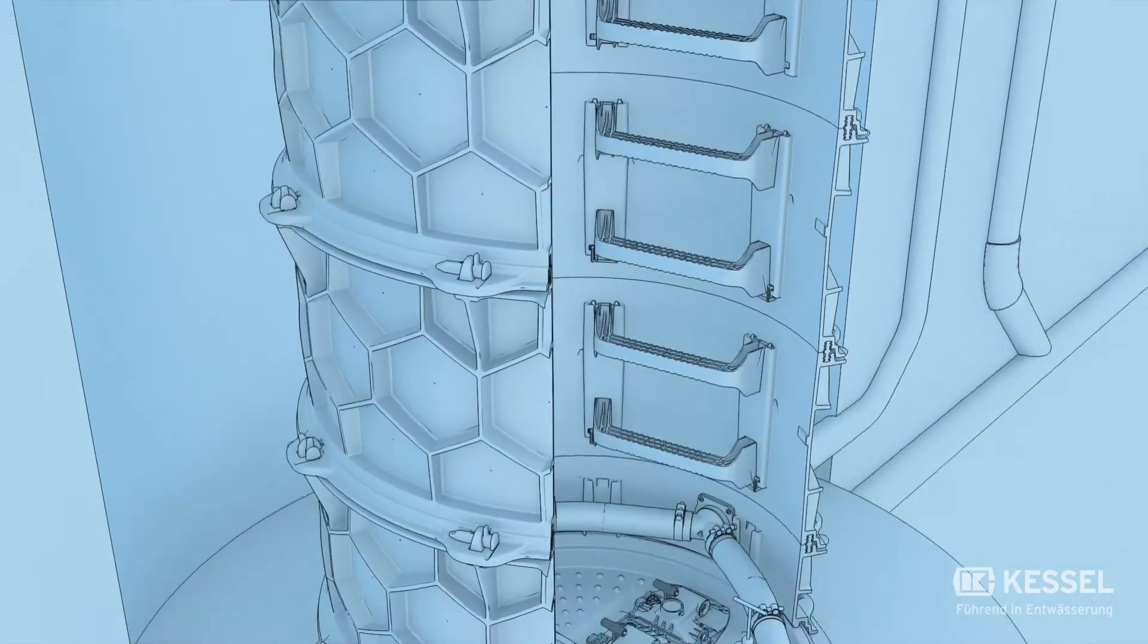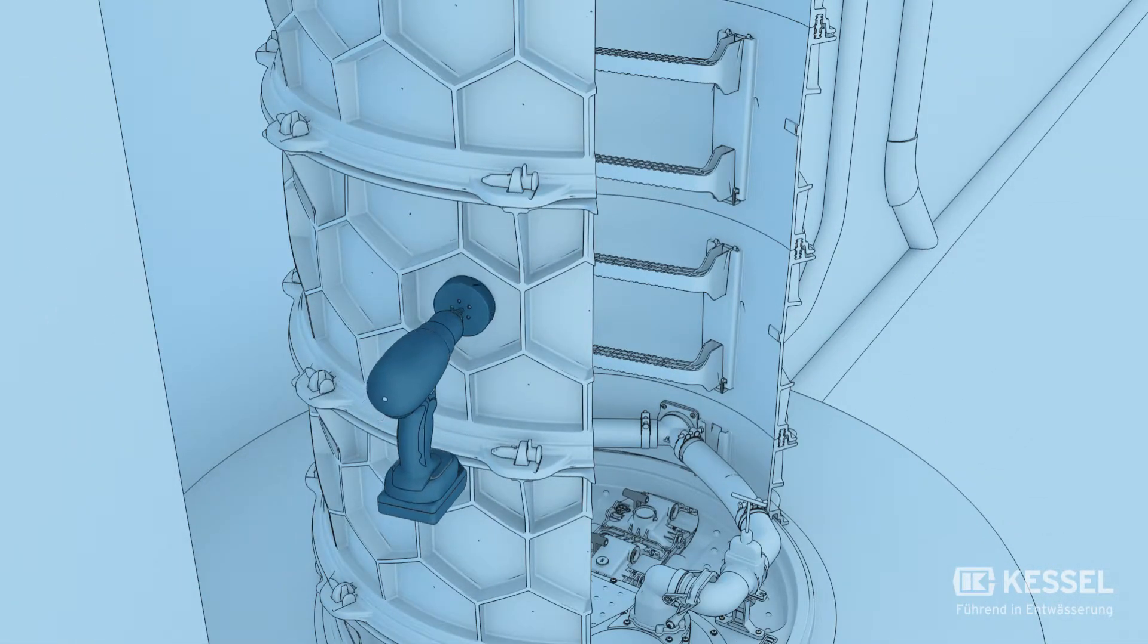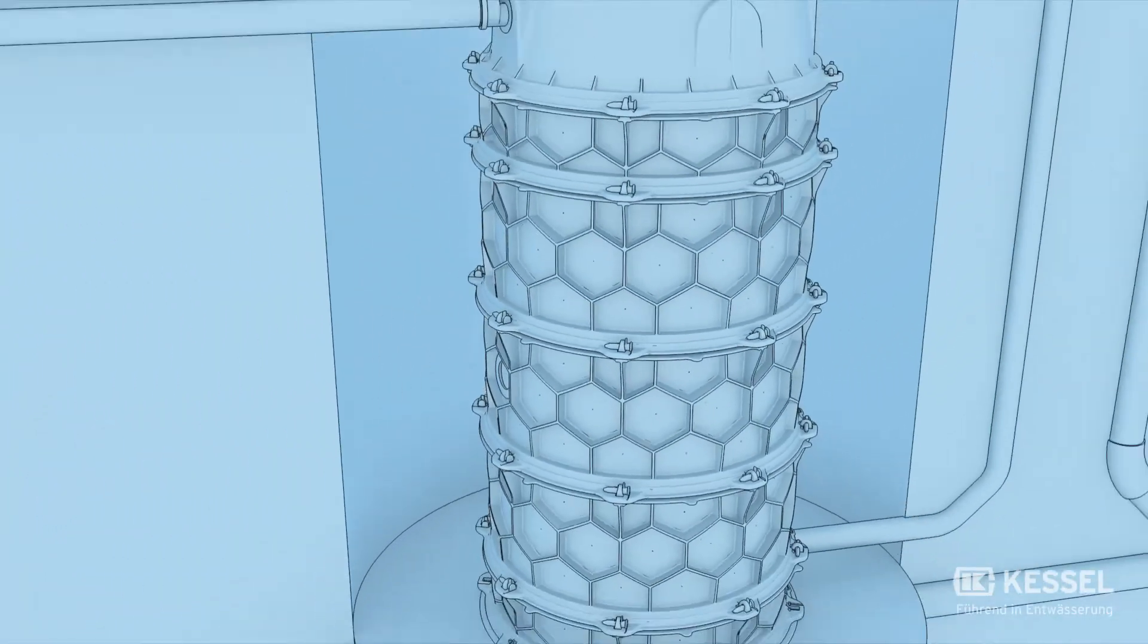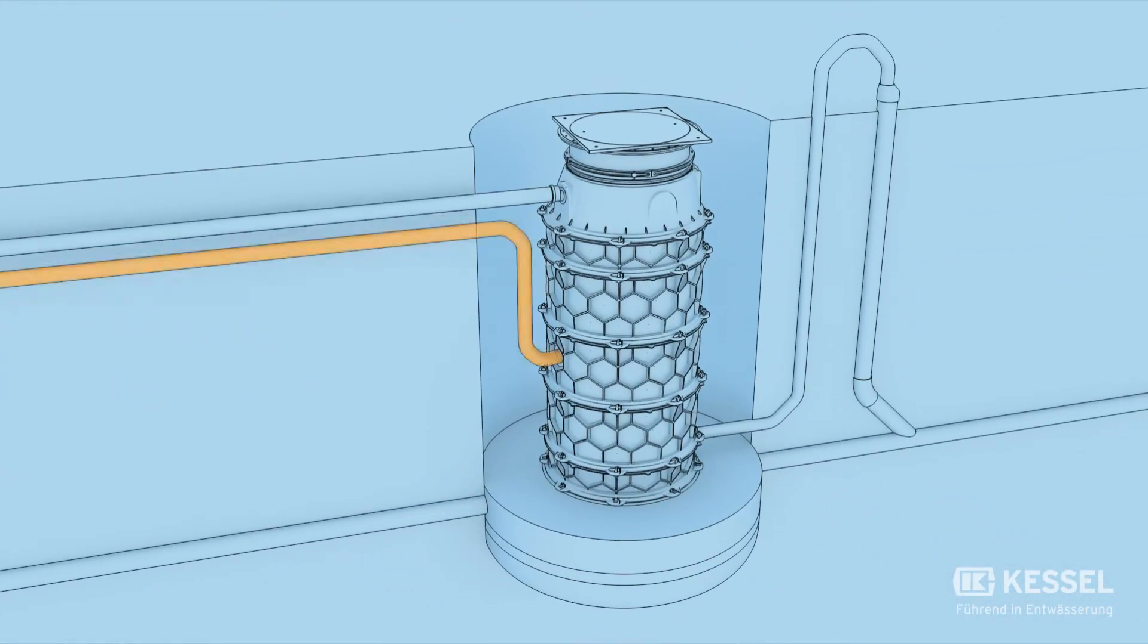Now, we drill a DN100 feed-through into a tapping surface or a tapping point and then insert the feed-through seal. We insert the cable tube into the feed-through and connect it to the switching device. Attention! The cable tube must be installed at an incline.